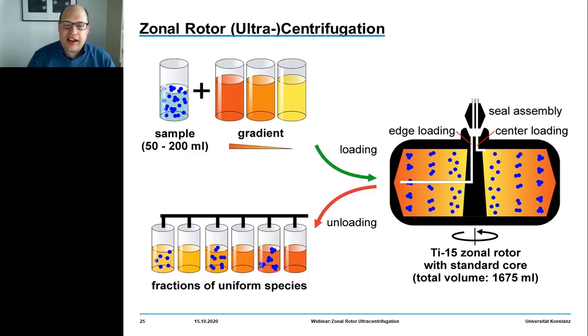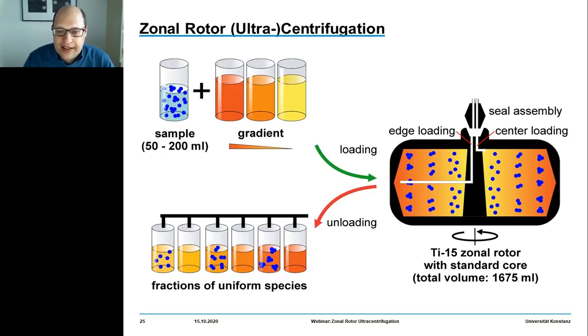This method has two major characteristics. The first is a bowl-shaped hollow rotor that replaces the need for centrifuge tubes. This hollow bowl-shaped rotor hosts large volumes of density gradients. The second important characteristic is that this rotor can be loaded and unloaded dynamically — meaning we can load the gradient and sample, and later harvest the zones of banded particles while the rotor is spinning — avoiding any reorientation of fluid layers and contributing to excellent sorting efficiency.